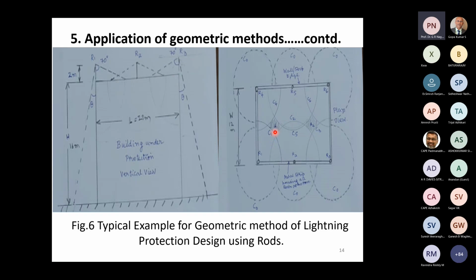So now you'll find that they are overlapping, but only two small areas are not protected according to the geometric method. But personally, I would feel that they get protected because the areas are very small compared to the spheres. Now outside, external to the building, these are the circles corresponding to the semi-conical angle of 20 degrees. We'll see that even though the height is very large, the circle radius at the ground level is very small. So it corresponds to only this radius from this ground point. So now this is how we apply the geometric method.